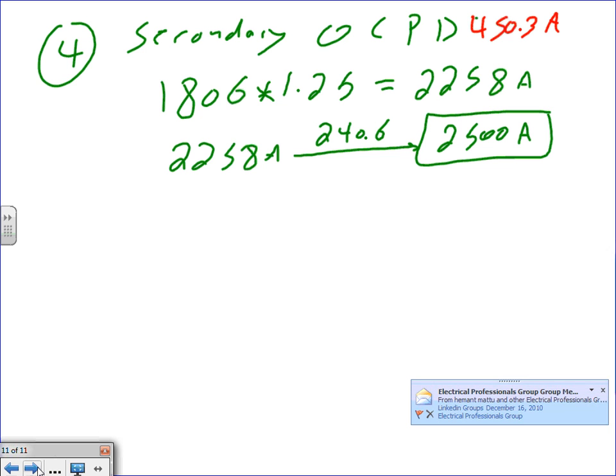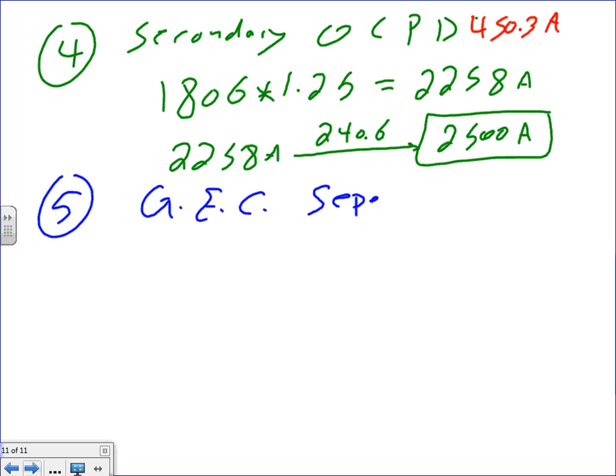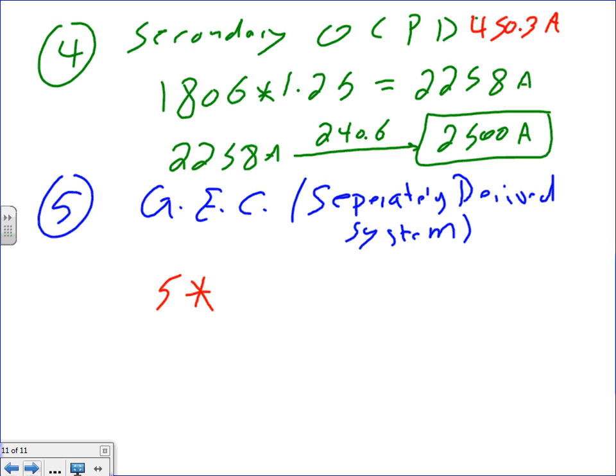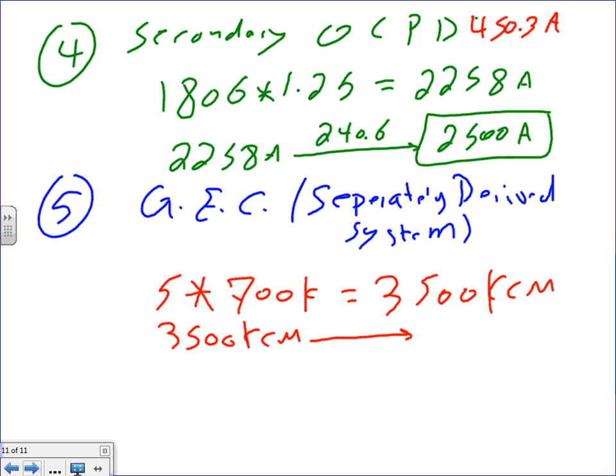Finally, Chad. We're going to go to 5. 5 is going to be the grounding electrode conductor for a separately derived system. I can't emphasize the words separately derived system enough. Okay, so how many runs did we run? We had 5 runs, times each one of them is 700 kcm. 5 times 7 is 3,500 kcm. Then you take the 3,500 kcm.